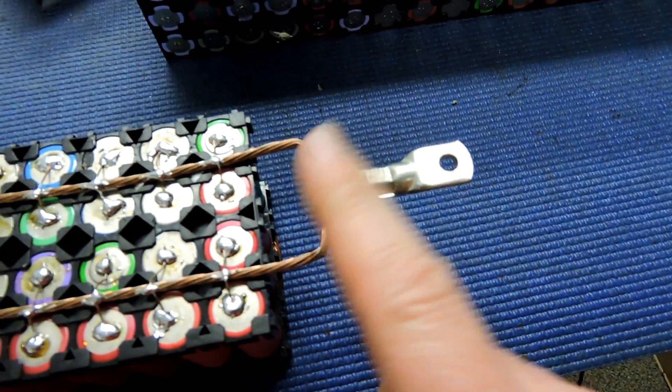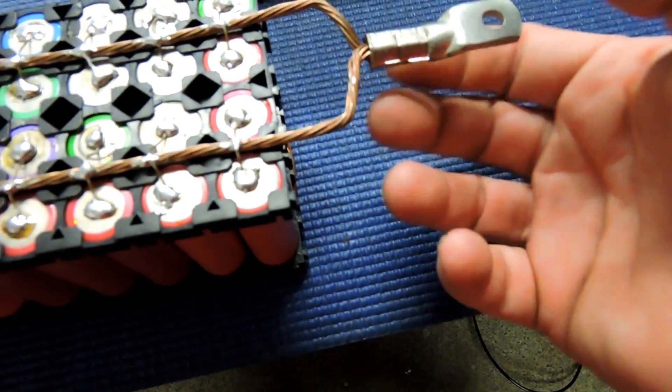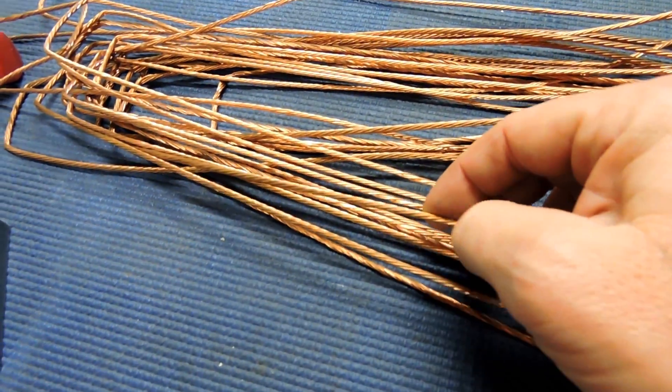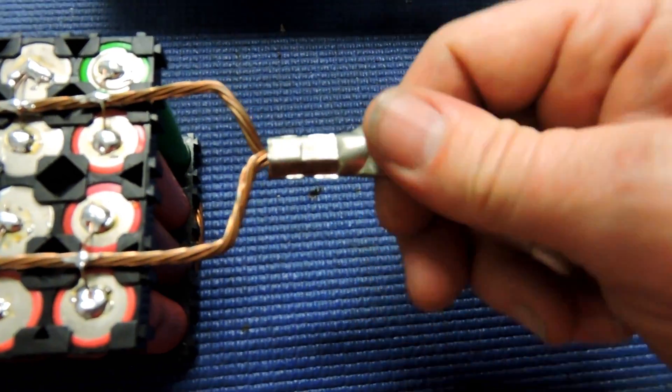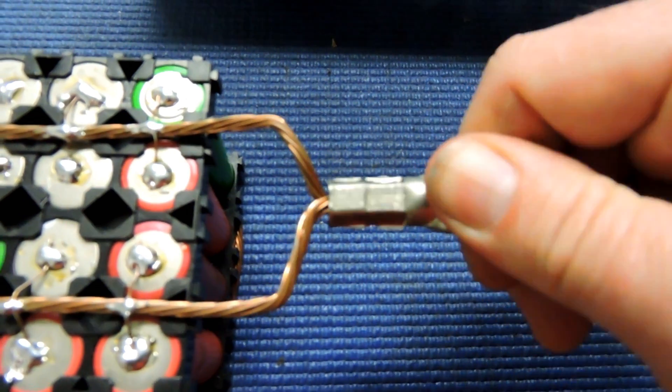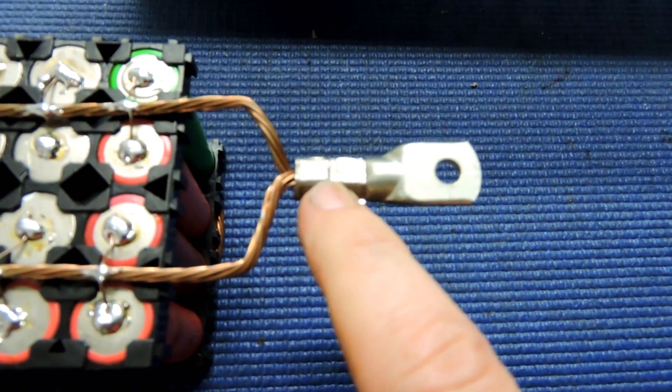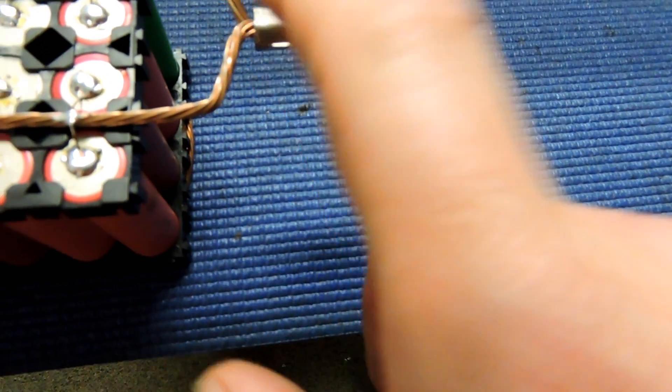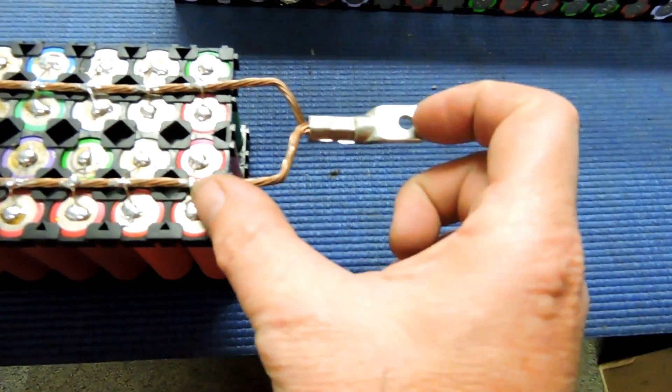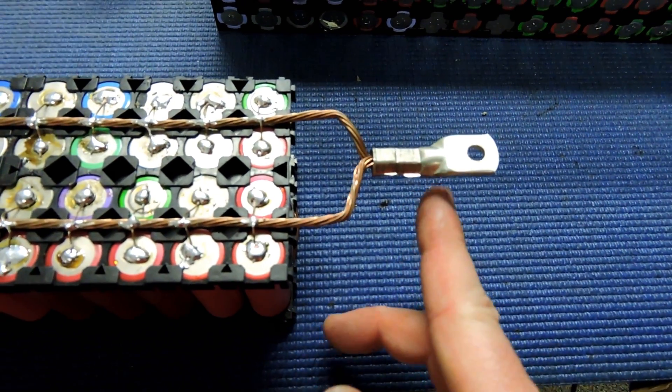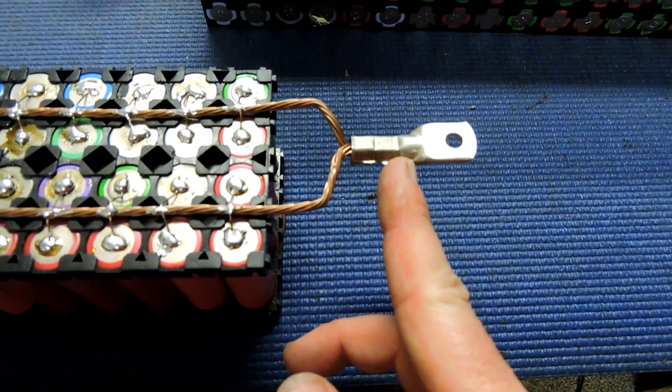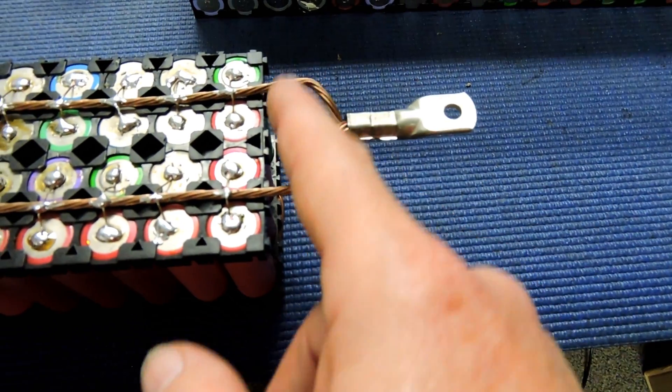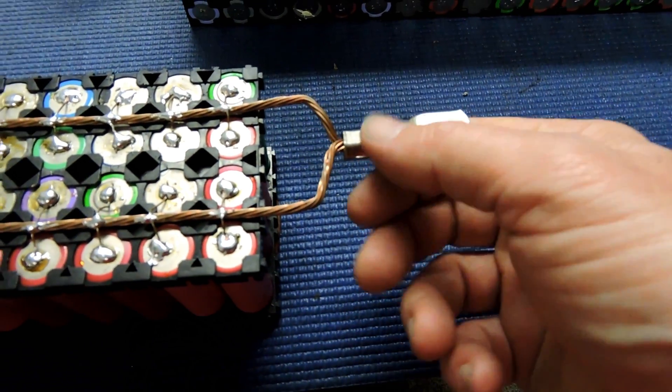Also I would have sized my wire a little bit thicker, because when I crimped it on here, on some of them they got - look, now that's not loose, which is good - but when I crimped them on they got a bit loose and then came out and caused a hot spot. So definitely two things I'd do better: do that a little bit shorter, maybe bring it to about here or something, and then I would have sized this wire a little bit thicker so we didn't have this crimping problem.